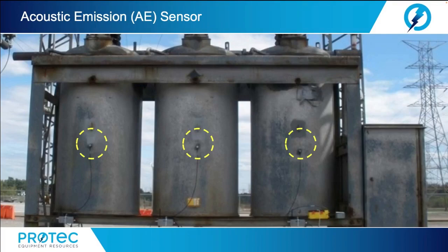Fluid and solid dielectrics such as oil, SF6, and resins will permit ultrasonic PD signals up to around 300 kilohertz. However, air cannot permit ultrasonic signals higher than roughly 80 to 100 kilohertz. To use the AE ultrasonic contact probe, it is best to apply a high vacuum silicon gel to the contact probe to bridge the air gap between the exterior of the tank and the contact sensor. This gel will conduct the PD signal from the exterior of the tank onto the ceramic head of the AE contact sensor.